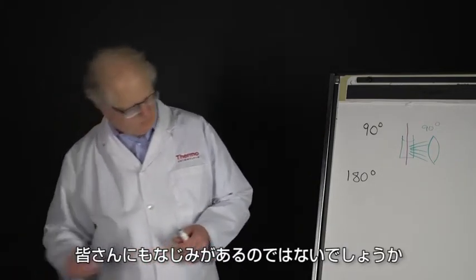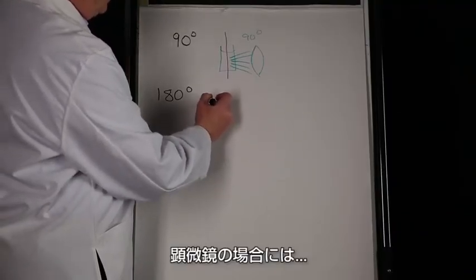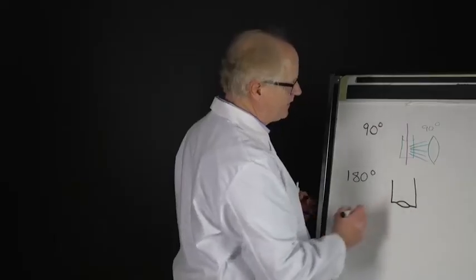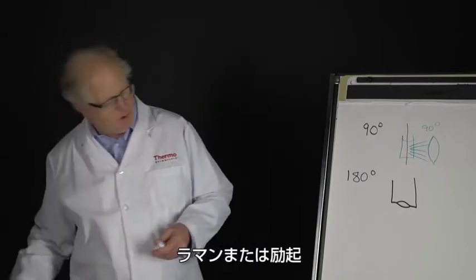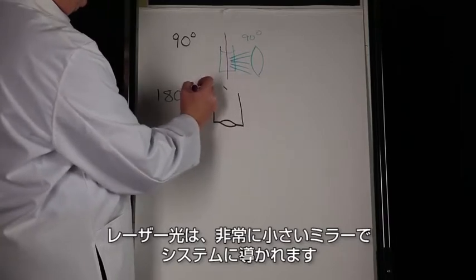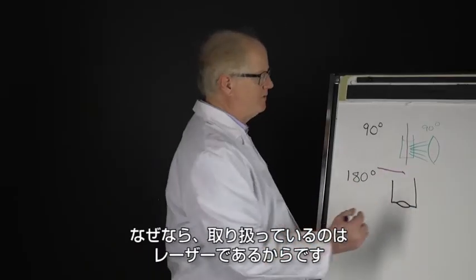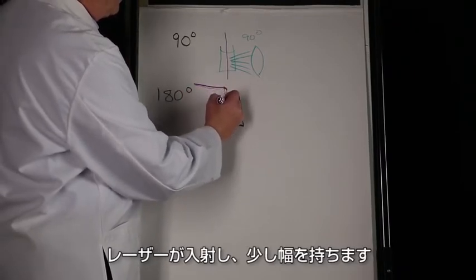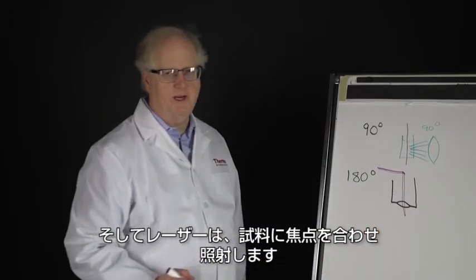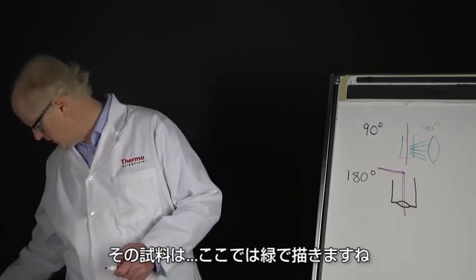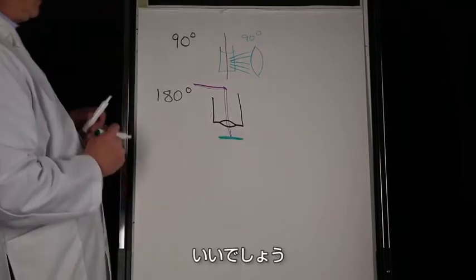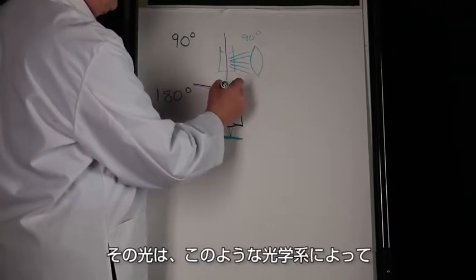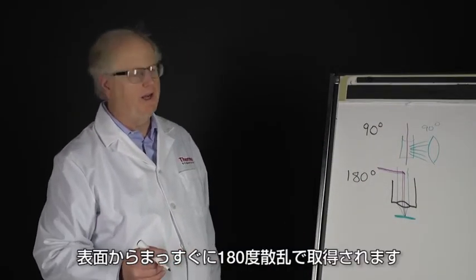With microscopes you'll see 180-degree collection is very common. So for a microscope — here is my microscope objective — the excitation laser beam is brought into the system with a small mirror, because you're dealing with a laser and don't need much of a mirror to bring it in. The laser comes through, focuses down onto the sample, which then scatters the Raman light back up through the system.